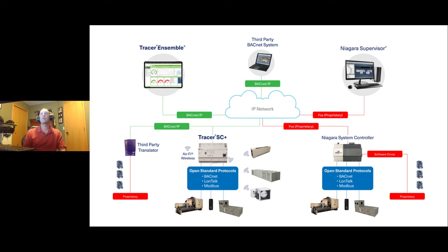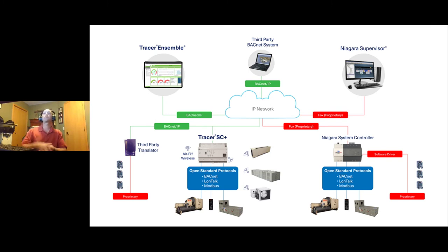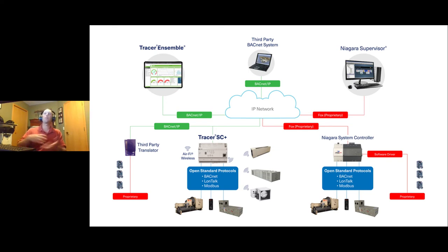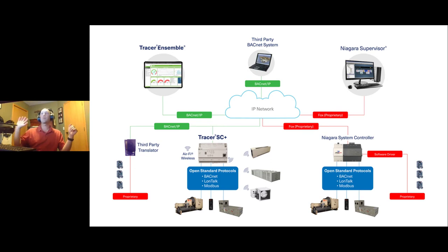By comparison, using a third-party translator device and making sure it translates proprietary communications and exports all data as BACnet over IP, you don't even necessarily need a Trane Tracer SC Plus system level controller — that's part of the point of building open systems. By ensuring it only speaks BACnet over IP out of the top, you can use many different supervisory controllers or pieces of software — Trane's Tracer Ensemble, any third-party BACnet system or tool, even Niagara Supervisor — all communicating through that translator just as expected from an open system.